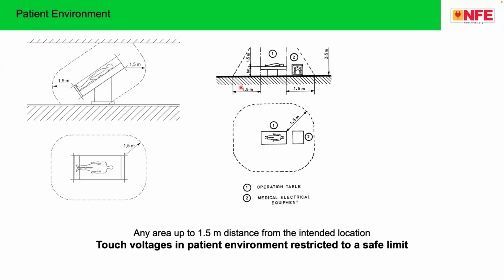Example, patient environment: an area up to 1.5 meter distance from the intended location. The patient environment is 1.5 meter. There is a chance that somebody may touch the patient, or somebody is standing there doing something with the patient. Somebody may touch a doctor who is touching the patient's body. The chance of touch is much more to the patient. The patient is already unconscious. He is connected with the medical electrical equipment, probably bypassing the skin. The chance of shock to the patient is extremely high. Within the patient environment, the chance of potential difference must be avoided so that the life of the patient is taken care of well.